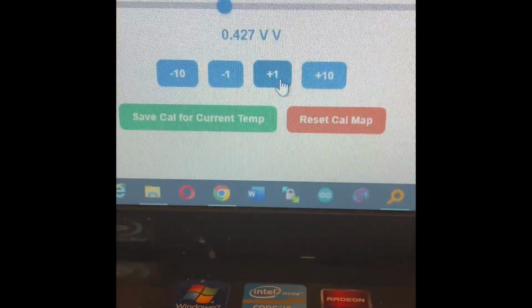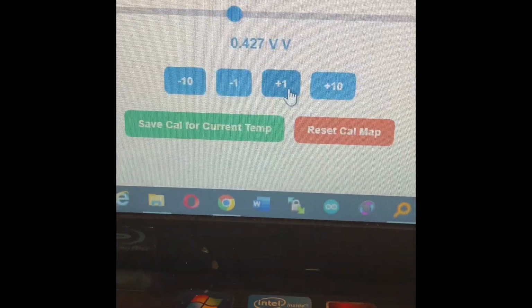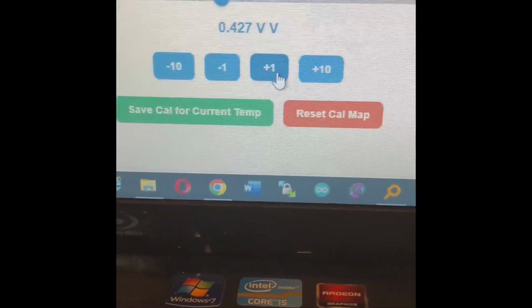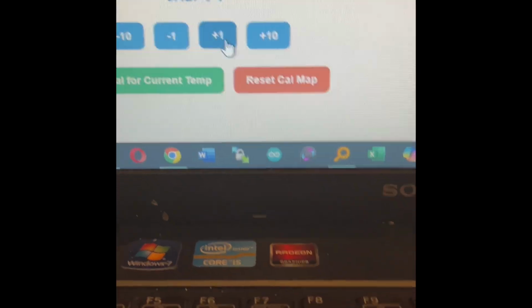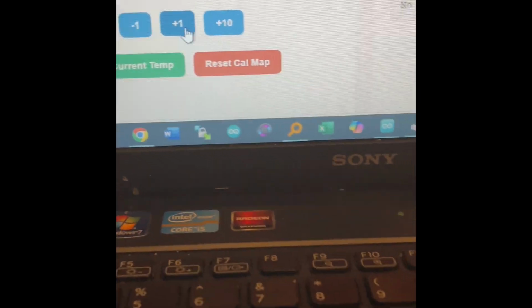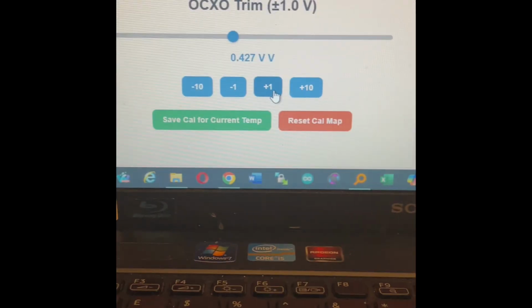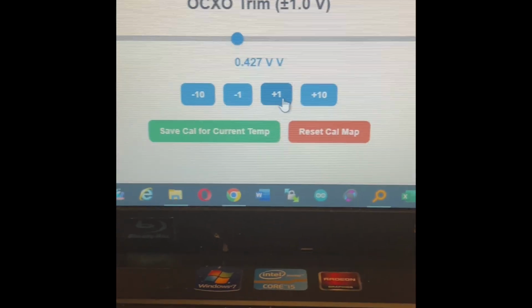But then obviously, if this temperature was here, if this was functioning, then I would hit this button here and say save calibration temperature. So we next know that when the thermistor is at this temperature, the program will automatically trim. So, in fact, it's working actually like a temperature compensated crystal oven. It's automatically compensating with time and with temperature, and it also trims. So there we go. I'll just hit this button, save calibration temperature, current temperature, and that would log it to this map here.